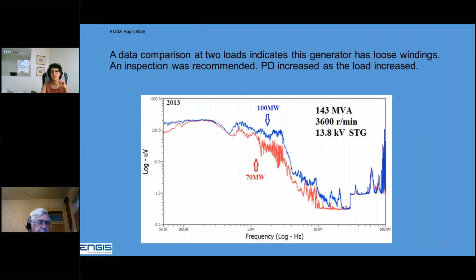Another thing that works quite well was pioneered by EDF in France with partial discharge testing on their big units. And that is comparing data at 2 different loads. So we try to do it as much as we can, as high a load as they can get, and then about 70% of that.